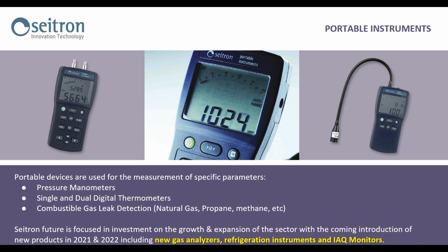For portable instruments, we have an array of pressure manometers and single and dual thermometers, but our most popular units here are our combustible leak detectors. They're one of the few on the market that actually give you a reading in both ppm and LEL, the lower explosive limit. It's a very unique product line because it gives you that reading, which is important for a lot of our utility customers who want to look at LEL.